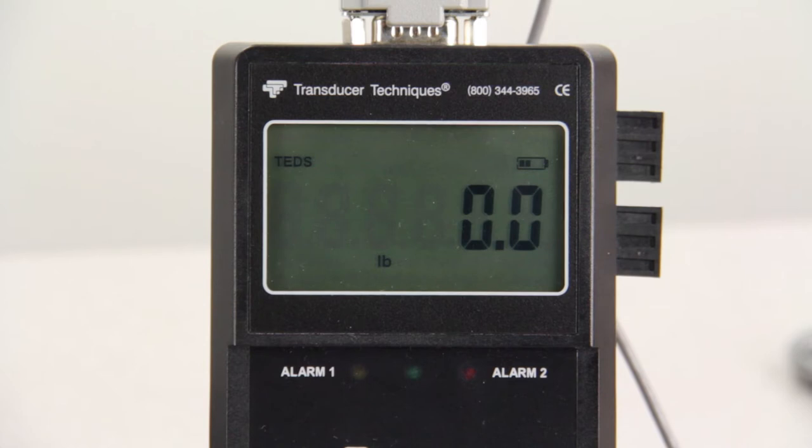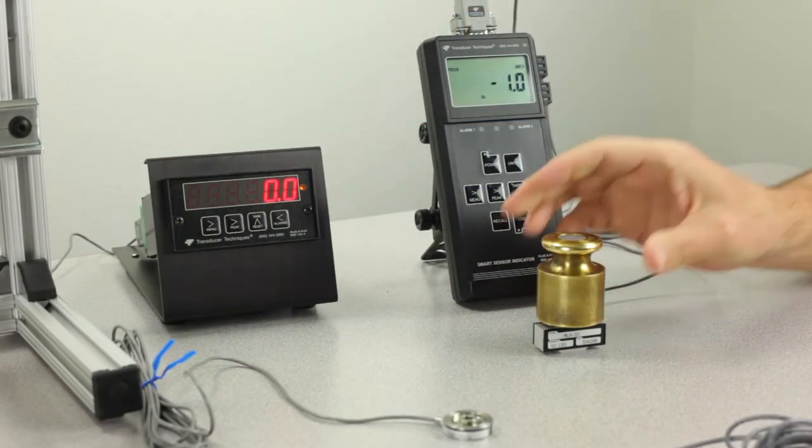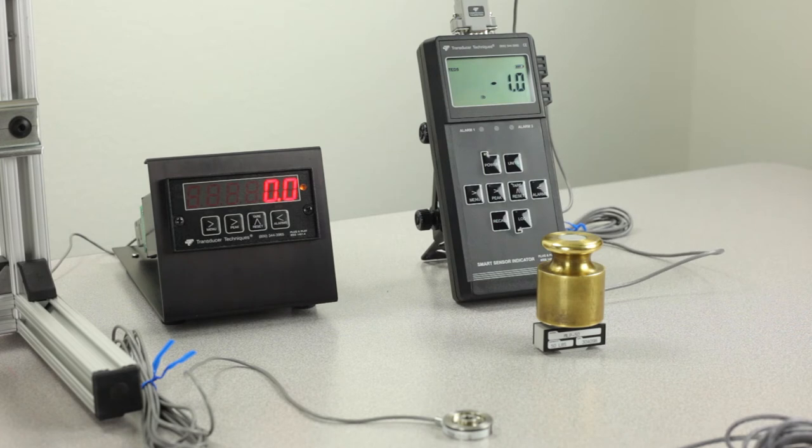The SSI is also showing pounds, letting the user know the engineering unit you're calibrated in. Now I'll put a 1 pound weight on the load cell and the display is reading 1 pound. You can also use a non-TEDS load cell with the SSI. I'll show you that calibration process in the SSI user video.